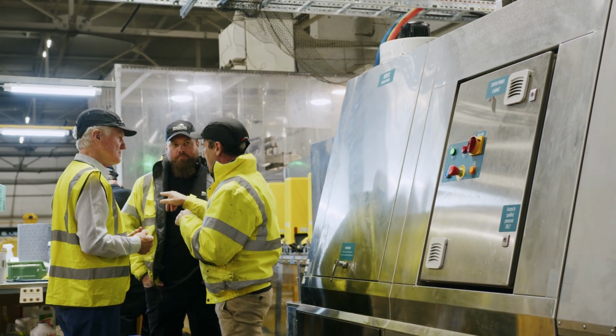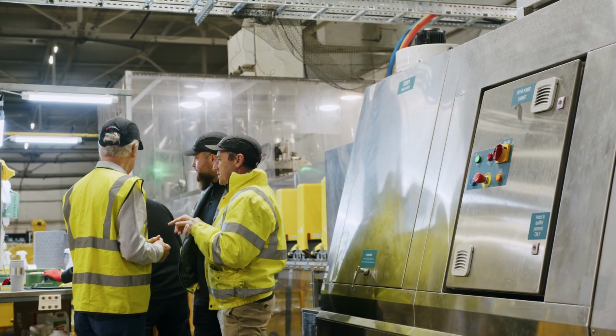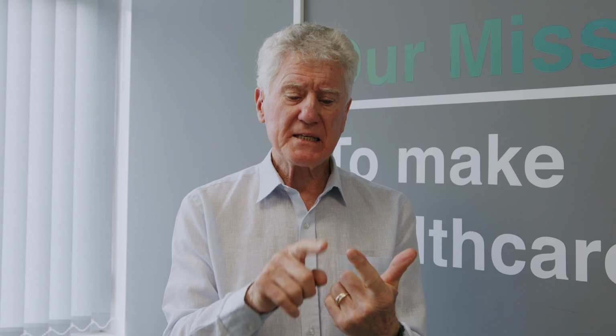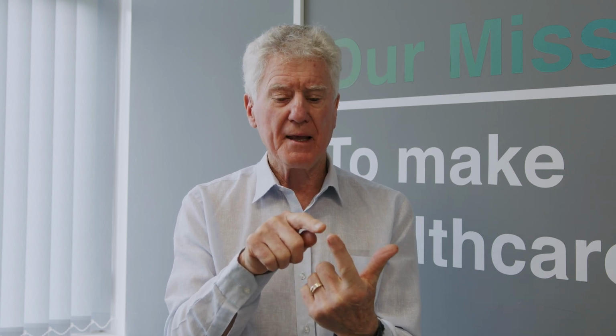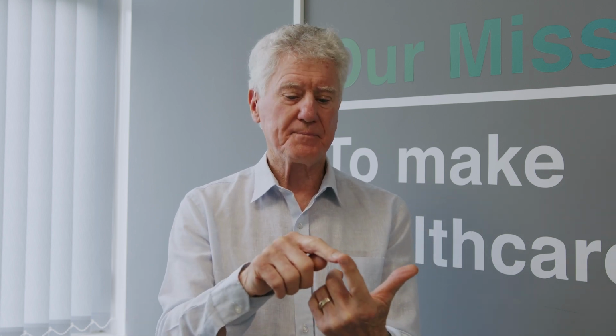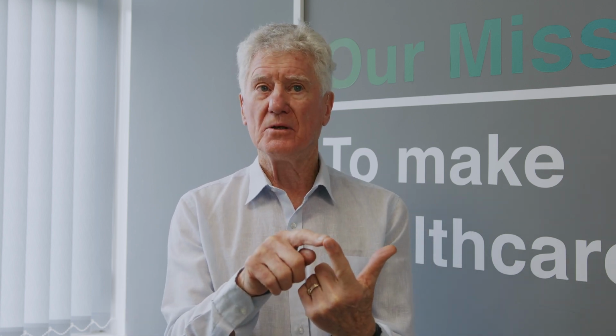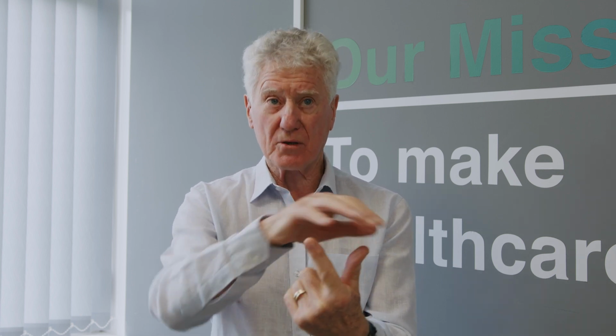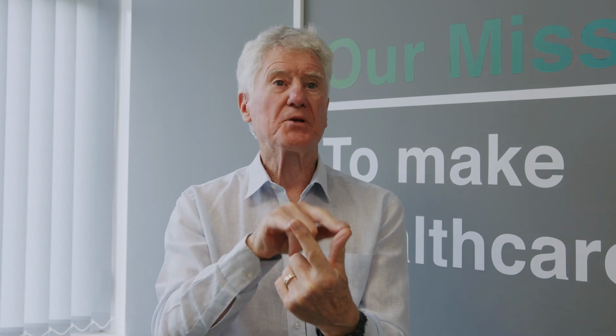It said, if you want to really test an endoscope washer, now that is high level disinfection, then you need to use 2 pathogens. The 2 pathogens stipulated in the British standard were Staph aureus, and the people watching this video will know that's the most common pathogen in a hospital, but it's pretty easily killed. So they said, we also would like you to add an organism called Enterococcus faecalis, which lives in our gut. And it's harder to kill, both chemically and by heat. They're not spores, they're called vegetative organisms, but they were the 2 in the British standard.